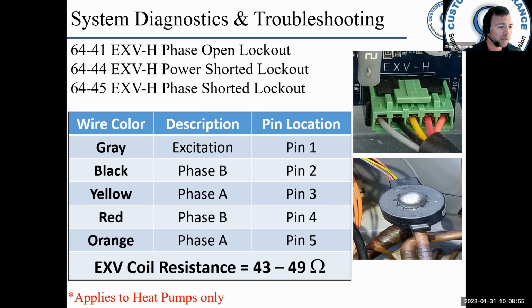Each time power is applied to the outdoor unit, the EXV will operate to a known position, as the valve does not have the capability to provide feedback on the actual position. So what the PCM software is doing is driving it to a known position and then keeping track of it. If it drives it all the way to, say, position 1, and then opens it up to position 50, it keeps track of that. If it has to adjust it to position 25, it keeps track. So anytime power is applied, it has to drive it to a known position and then keep track and remember where it is, because it will not provide feedback.